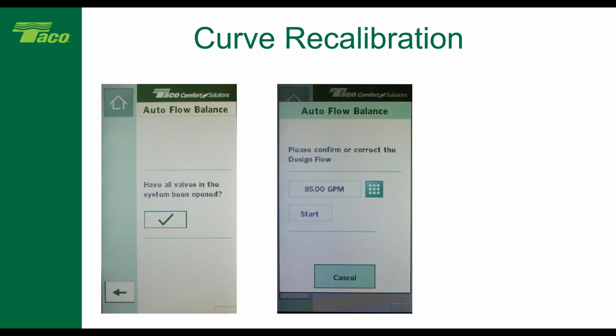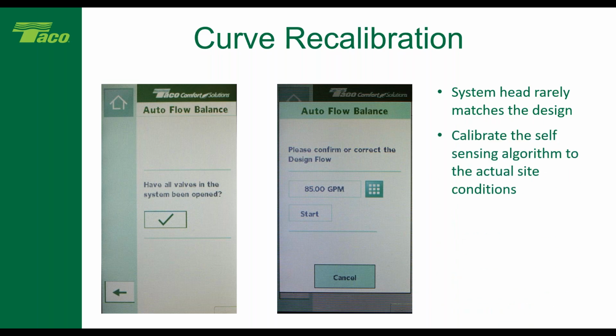So it marks that number, and it's going to ask you to close all the control valves. And it's going to slow that pump on back down, and it's going to figure out what the bottom end or that minimum control set point is. Now it's going to come up and ask you, hey, here are the new values. Do you want to accept them? You tell it yes. And now you've recalibrated the control curve to match the actual system the way it's installed. Okay, this recalibrates that self-sensing algorithm to the site conditions perfectly.